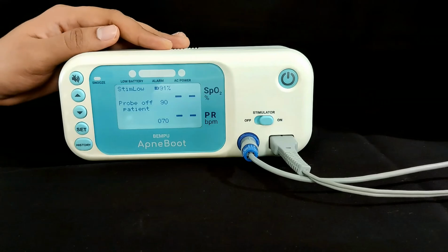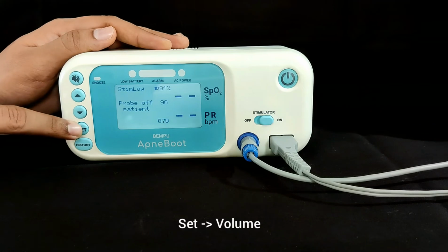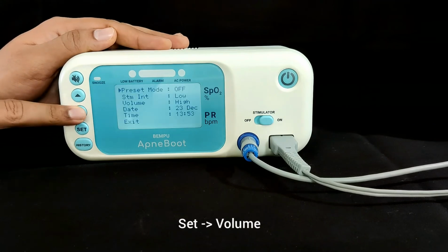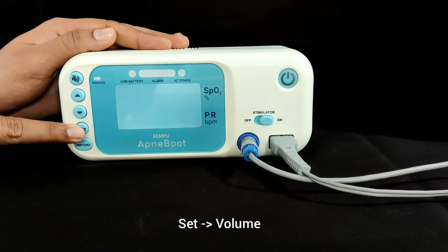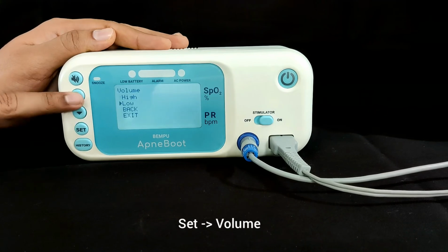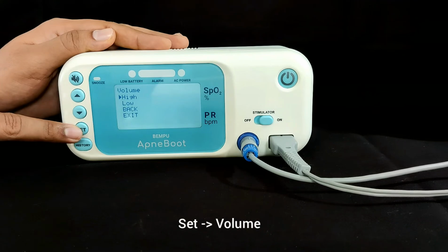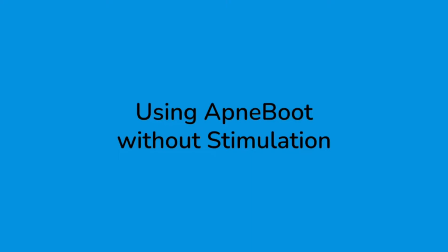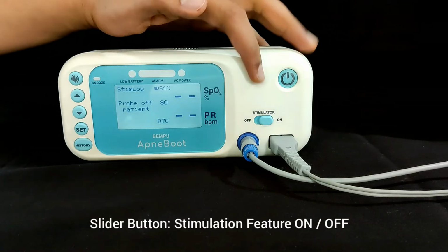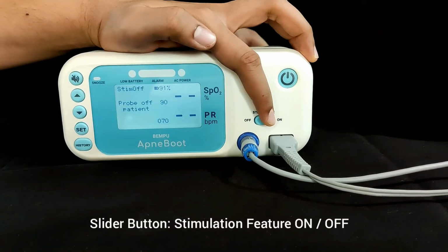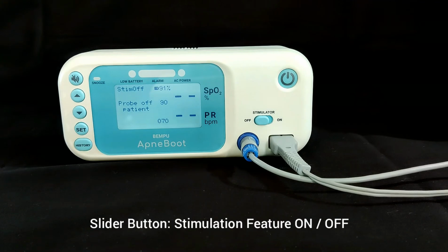You can also customize the alarm volume as needed to high or low. To do so, press the Set button, select Set Volume, then select high or low using the arrow up and down buttons. Press Exit to save the settings. You can also use the ApneBoot without the stimulation feature. To do so, turn the slider button to off position. This will make the device function only as a standard pulse oximeter.